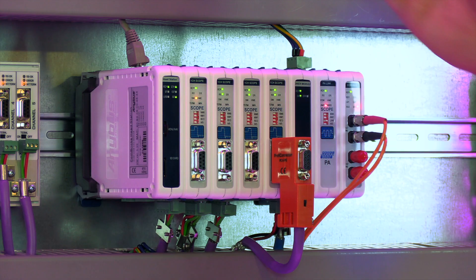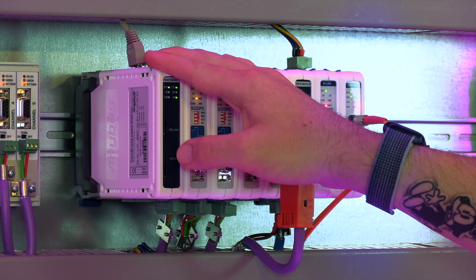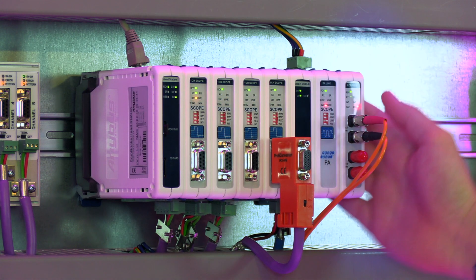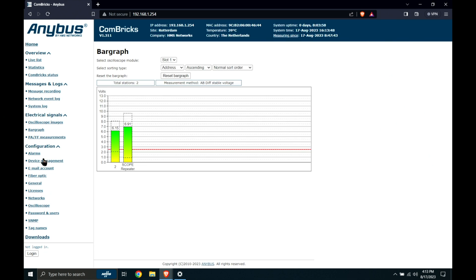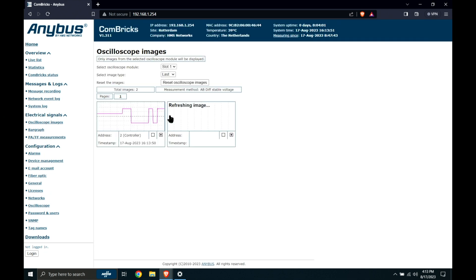All we need to get started to get your Combricks running is you need a headstation, and depending on your process, you can add your Profibus DP, PA, or even fiber optic cards. Once installed, the Combricks provides its own integrated web server, so all you need to do is open your browser, navigate to the IP address of the headstation, and you're in. No need for any extra added software.